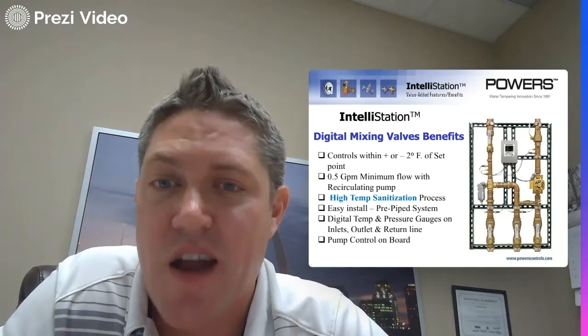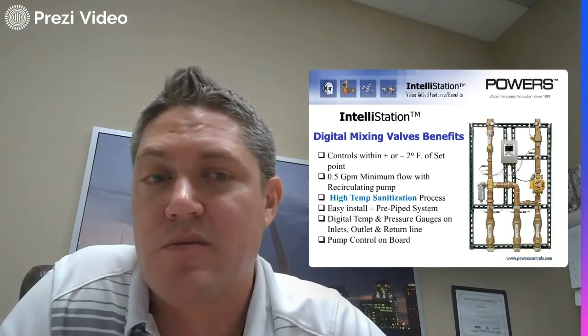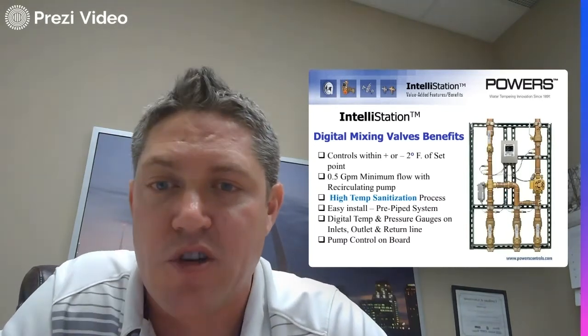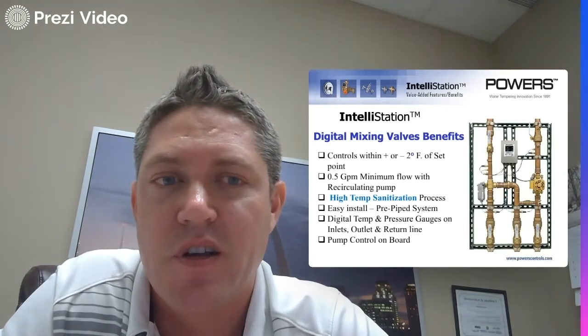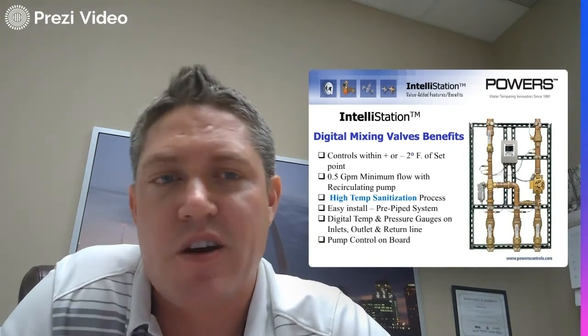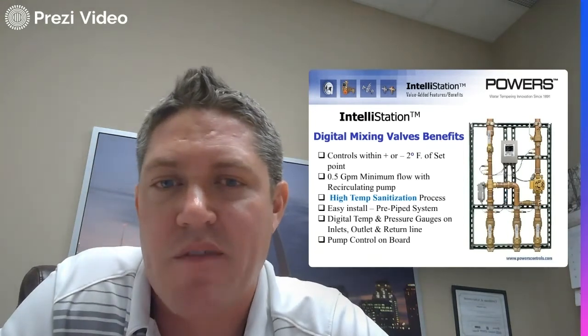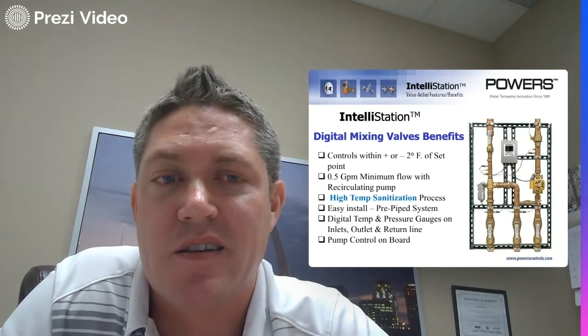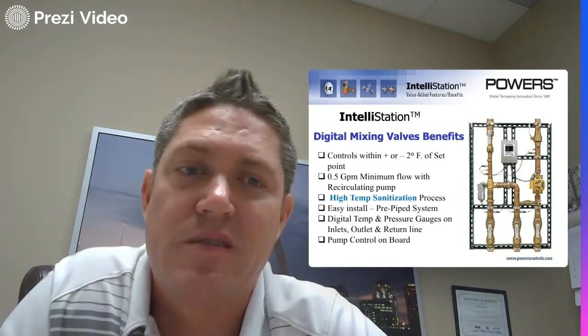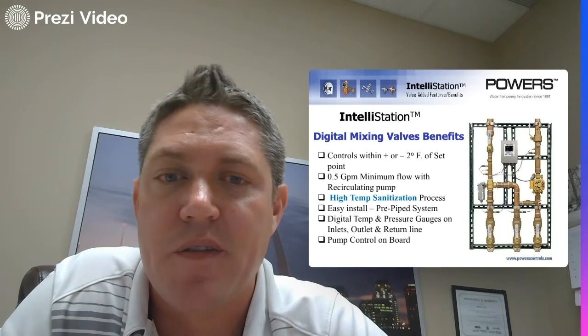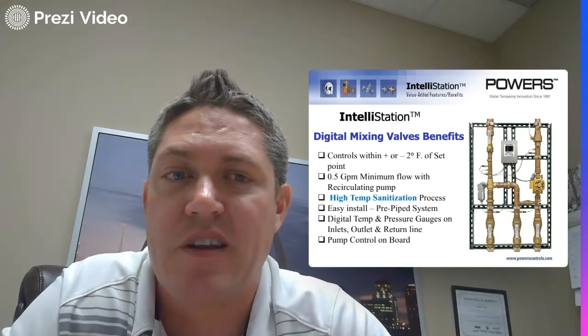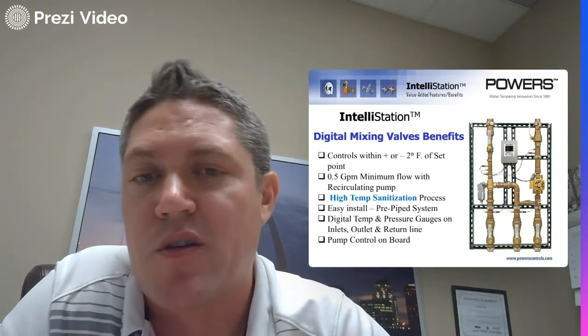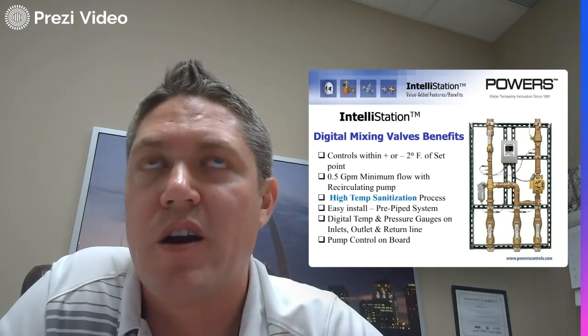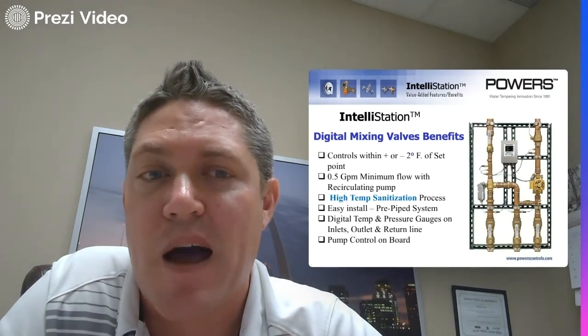It eliminates the need for an aquastat, but you can always just put it in always-on mode too, which is probably the preferred setup, because turning them off and on just shortens the life of the pump. And because this thing is self-balanced, there's really no need to be turning the pump on and off. But either way, it can be done through the controller, so you don't have to have an aquastat or a separate power source for the pump.